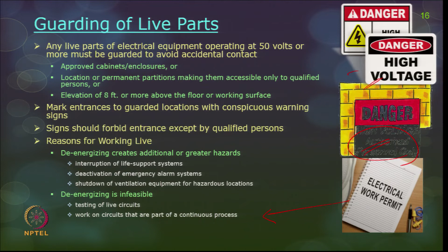Sometimes de-energizing is not feasible. Suppose you have to test a live circuit, then you may have to keep the current on. Another case is working on circuits that are part of continuous processes, where you won't be able to trip off and then work. So, sometimes you cannot de-energize the lines, and you have to be very careful with live wires. In those situations, the only way is to get a proper electrical work permit. You should know what the hazards are, what the nature of work is and so on. Accordingly, get a proper electrical work permit before you start working on live parts.